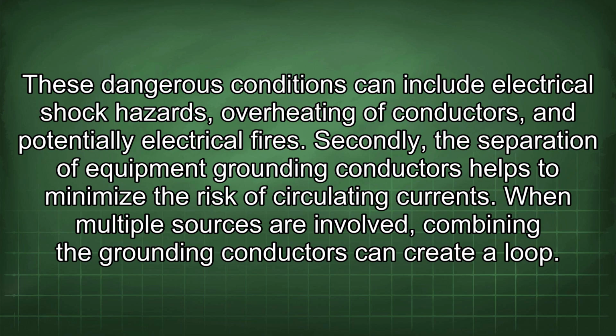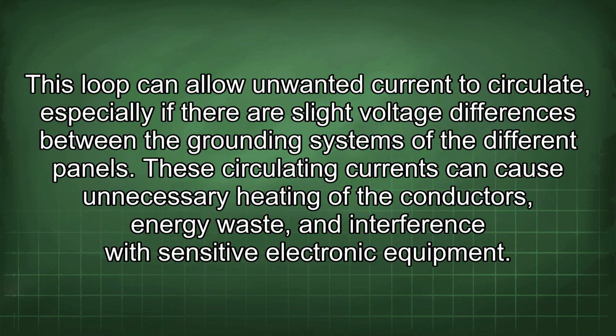Secondly, the separation of equipment grounding conductors helps to minimize the risk of circulating currents. When multiple sources are involved, combining the grounding conductors can create a loop. This loop can allow unwanted current to circulate, especially if there are slight voltage differences between the grounding systems of the different panels. These circulating currents can cause unnecessary heating of the conductors, energy waste, and interference with sensitive electronic equipment.